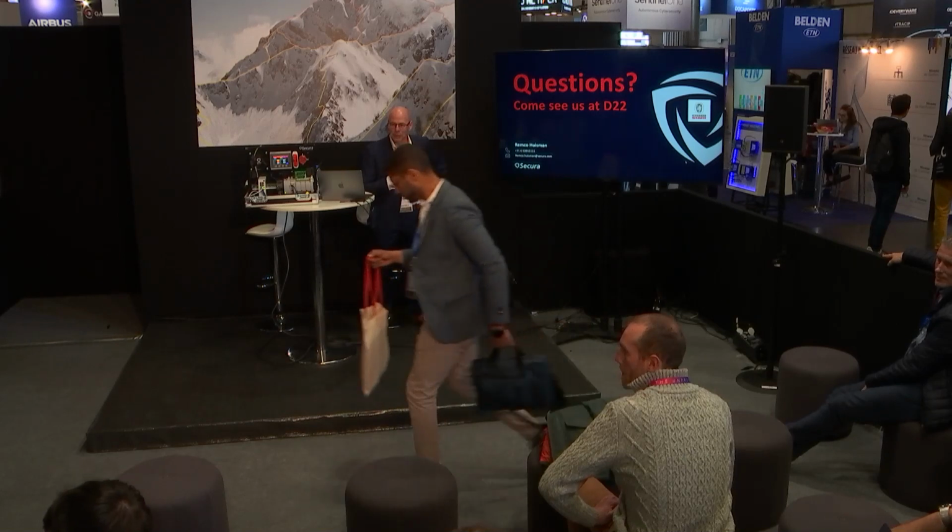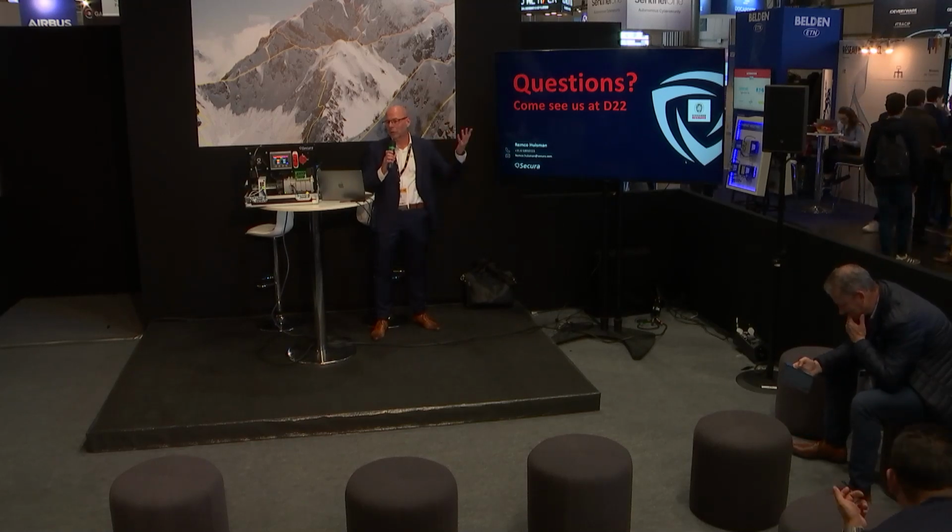Thanks for your presentation. You talked about network segmentation. Can you explain how that works in practice on OT? Well, for example, you can make separate VLANs to make it more difficult. VLANs are not the holy grail, but you can make it more difficult. You could install firewalls, like filtering Modbus traffic, for example. There are all kinds of things you might do. There are also intrusion detection systems from vendors that are out here, like Forescout and Nozomi, for example.